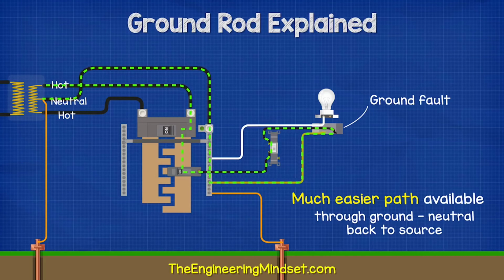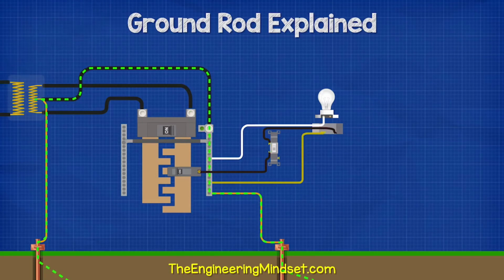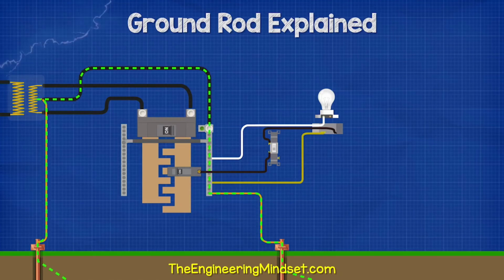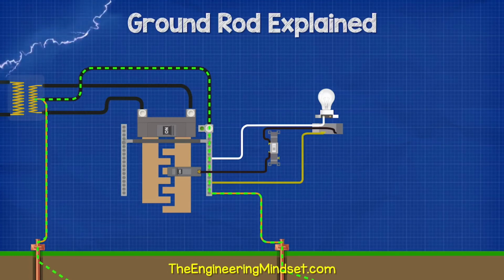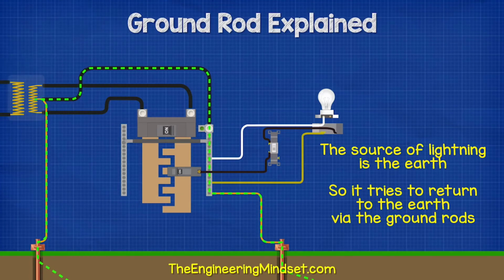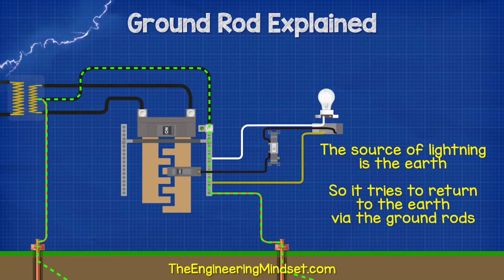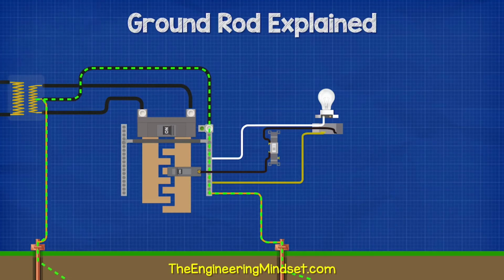When it comes to lightning, the source of lightning is essentially the earth, so lightning is always trying to get back to it. If lightning strikes the utility cables, it will flow along the wires to the ground rods of both the transformer and your main panel, trying to get back into the earth. If it wasn't for this, it would blow all our circuits and cause house fires.